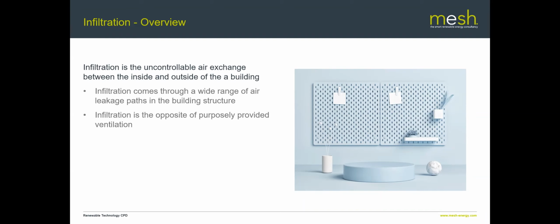So it is the opposite of purpose-provided ventilation. And what we're going to spend most of today talking about is purpose-provided ventilation. Infiltration is generally bad, and we want to minimize it. Now, we're going to caveat that a little bit later on when we're talking about retrofitting, because in some buildings, the purpose-provided ventilation wouldn't actually be sufficient without the infiltration. So we then have to think about, if we're improving the infiltration, how we then offset that by providing more purpose-provided ventilation.